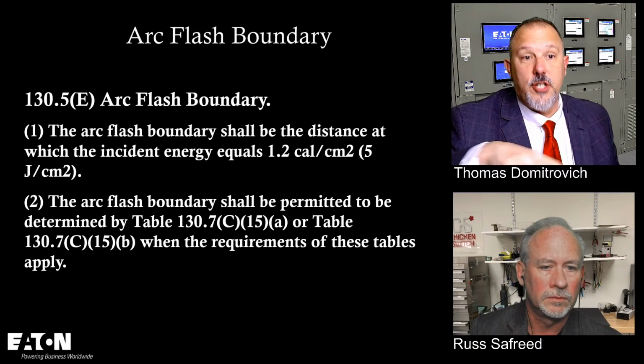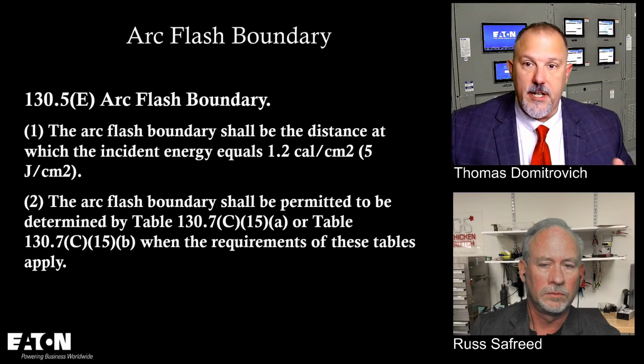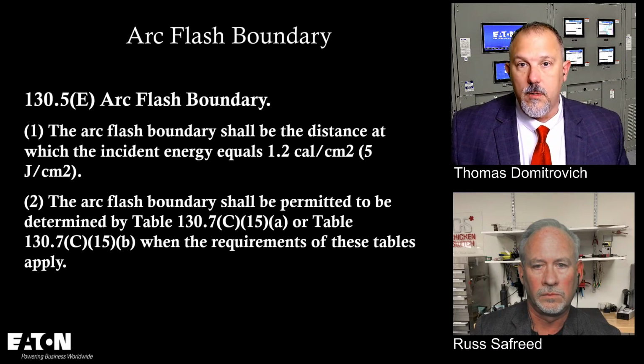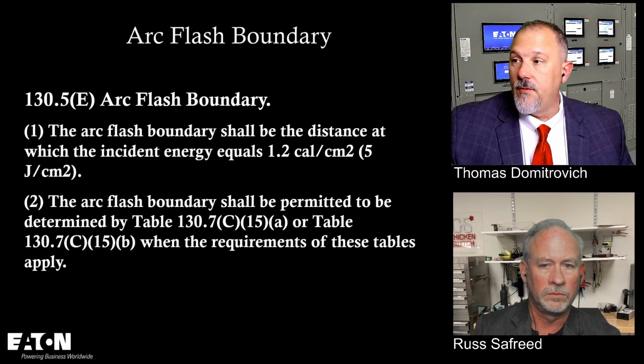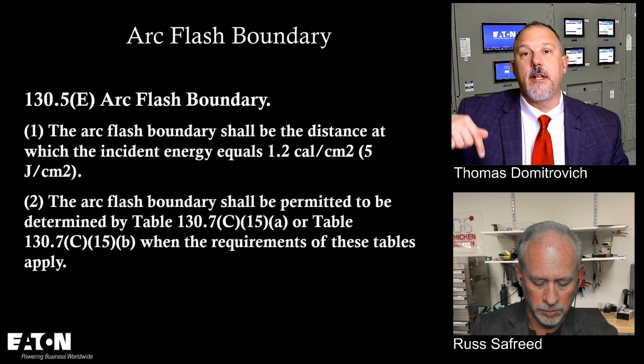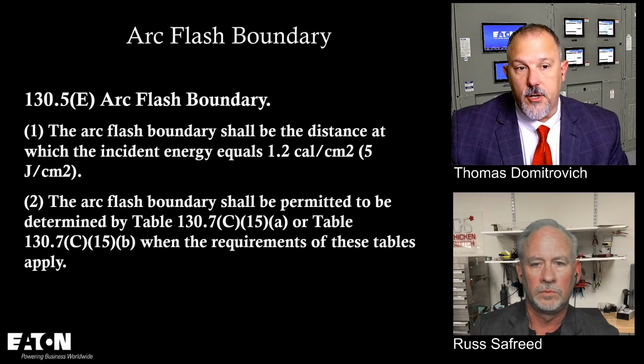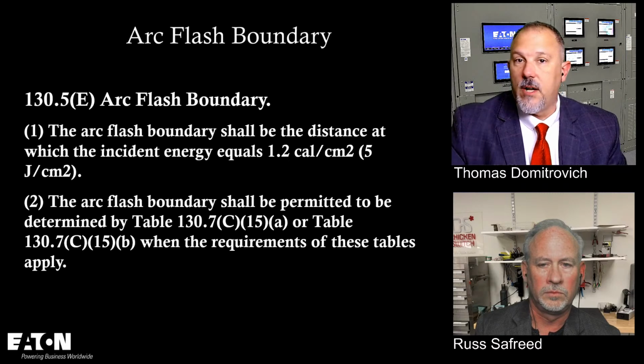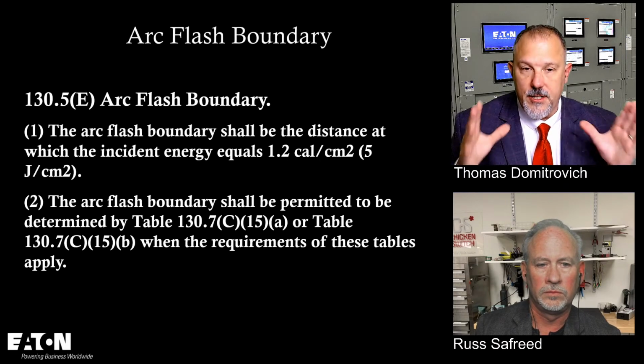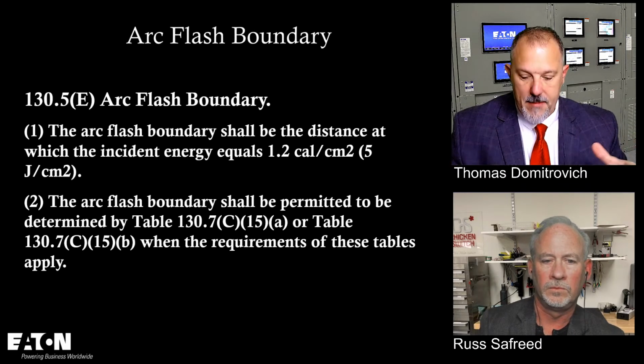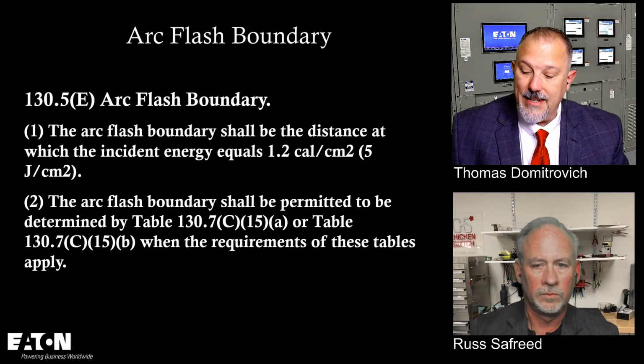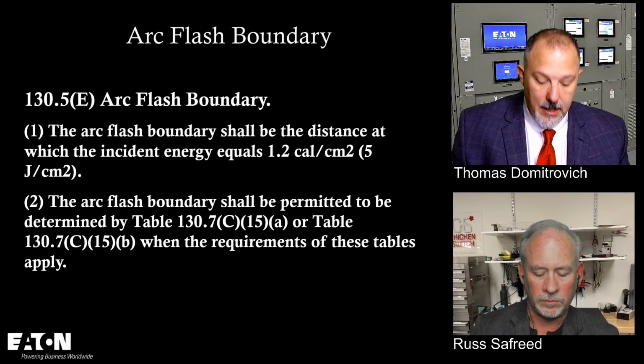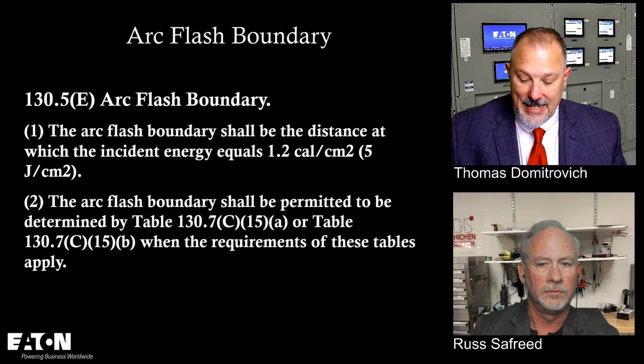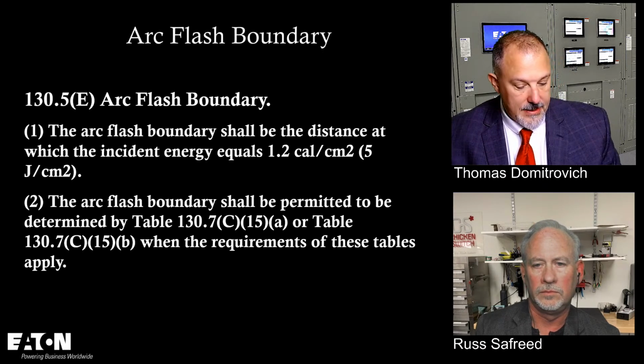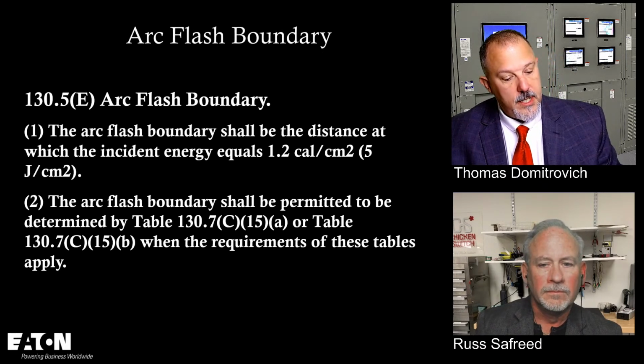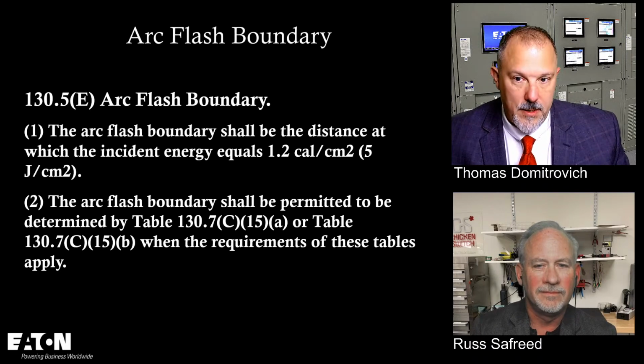And now to determine the incident energy, I can run a calculation, and I use IEEE 1584. On this channel, we have done that. We've already gone through short circuit calculations, and we've calculated incident energy and arcing currents, all of that good stuff. We talked about the clearing times and how to determine incident energy. So I can do that by the math, or 130.7 in the NFPA 70E. 130.7 is titled Personal and Other Protective Equipment.